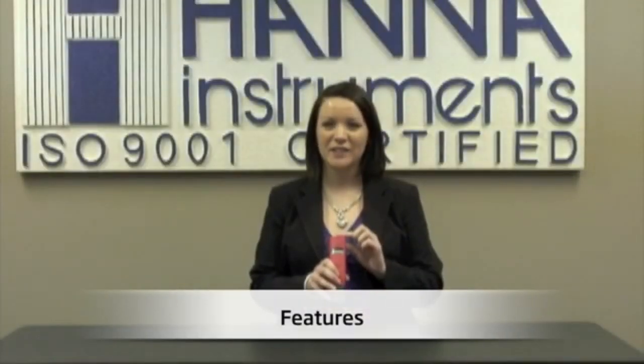I have my calibration certificate, I have my instruction manual, I have the instrument itself, and I also have a screwdriver for calibrating. So I'm going to give you a quick overview of the instrument. Here at the top we have our on-off switch. Down here we have our 2-point calibration. Then I'm going to remove the cap, and inside you're going to see the pH probe and also an extractable junction.